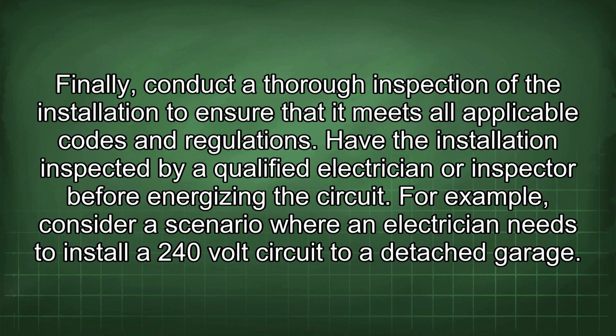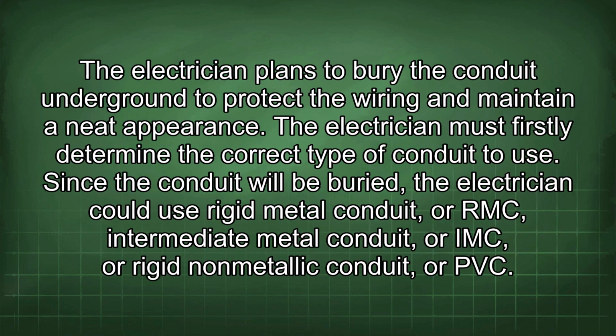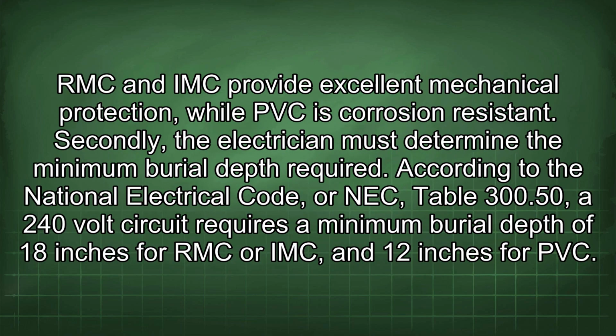For example, consider a scenario where an electrician needs to install a 240-volt circuit to a detached garage. The electrician plans to bury the conduit underground to protect the wiring and maintain a neat appearance. The electrician must firstly determine the correct type of conduit to use. Since the conduit will be buried, the electrician could use rigid metal conduit, or RMC, intermediate metal conduit, or IMC, or rigid non-metallic conduit, or PVC. RMC and IMC provide excellent mechanical protection, while PVC is corrosion resistant.